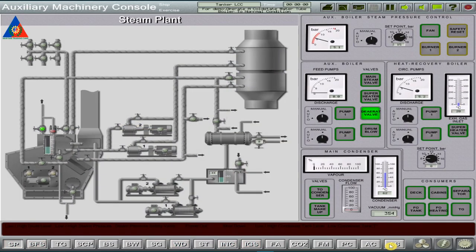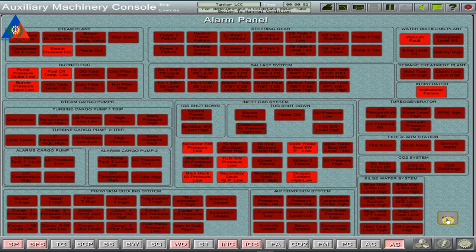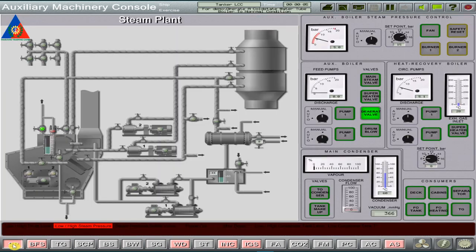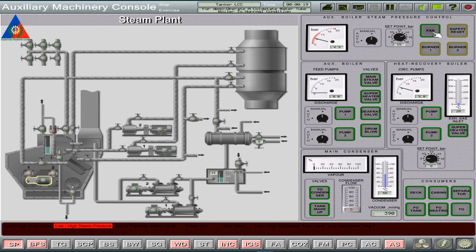We first acknowledge all boiler alarms on the alarm station page. On the steam plant page, close first the deaerating valve to prevent steam from escaping from the boiler drum. Next, turn on the fan to pre-purge all flammable gases inside the boiler furnace.